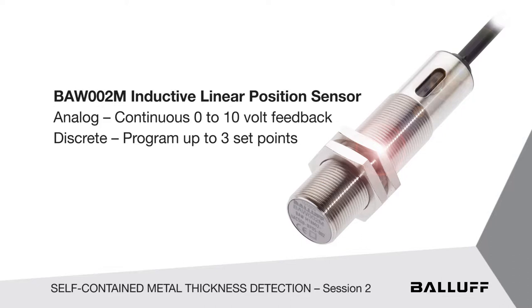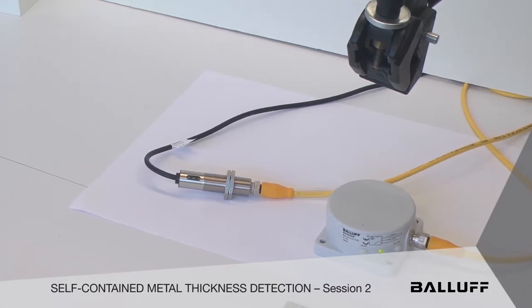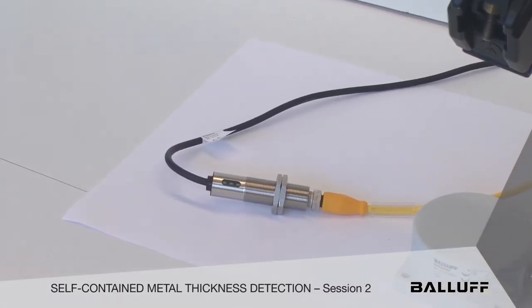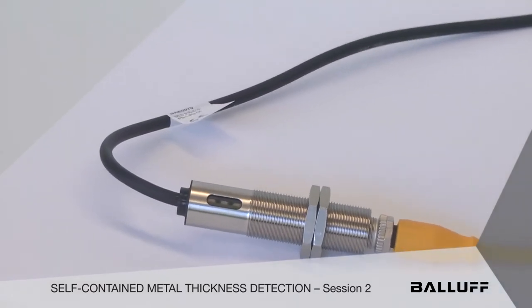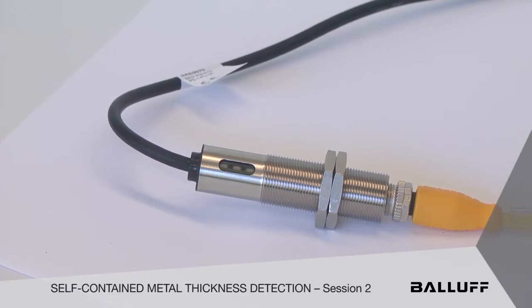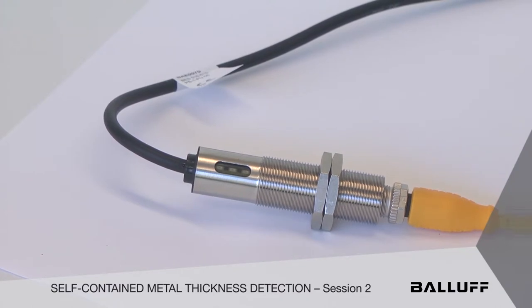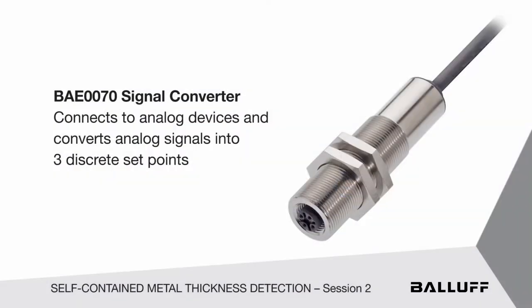It eliminates an extra cost for an analog input card into your PLC. But there's another little tool that you might find interesting. What you're looking at right now is basically what looks like the same unit — 18mm in diameter with three discrete set points built in — but it's actually a receptacle. Any analog device that Balluff manufactures can plug into this receptacle, and you can convert this signal into three discrete set points if you so wish.